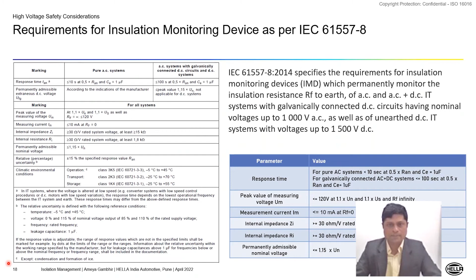Now let's talk about the basic IMD that many tier ones have implemented in vehicle. Mostly this is part of battery management system. So we have two measurement methods to have an IMD. Basically this is the high voltage line, let's say battery positive. This is the low voltage line, which is battery negative, and this is the protective earth terminal, which is shown with this color. And RF plus, RF minus are basically the leakage resistances or fault resistances.